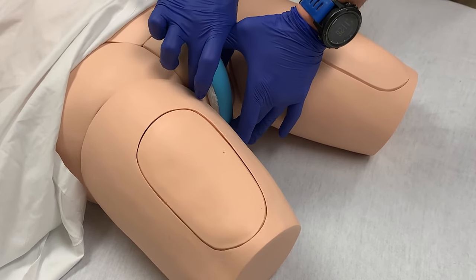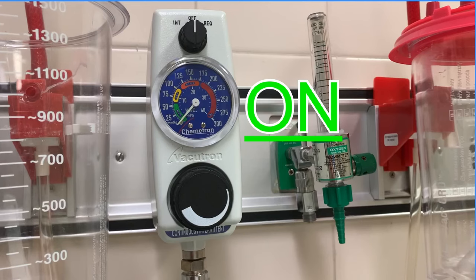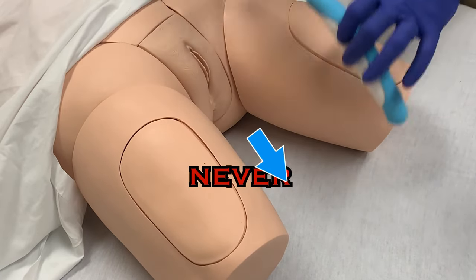To remove the PureWick, simply spread the labia and pull the device away from the patient. Suction should remain on during removal to minimize any urine spilling from the catheter or tubing. Never drag the PureWick up or push it down to remove it, as this can cause irritation and damage to the patient's skin.